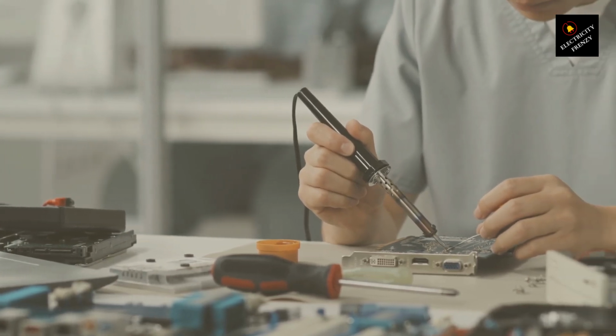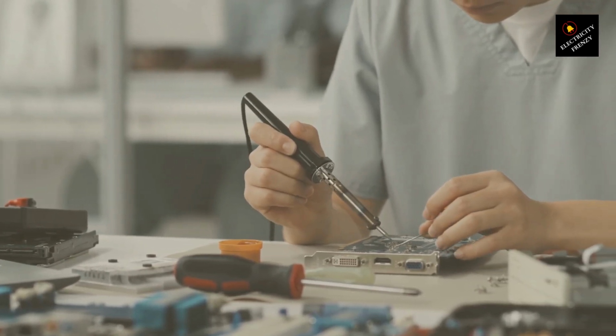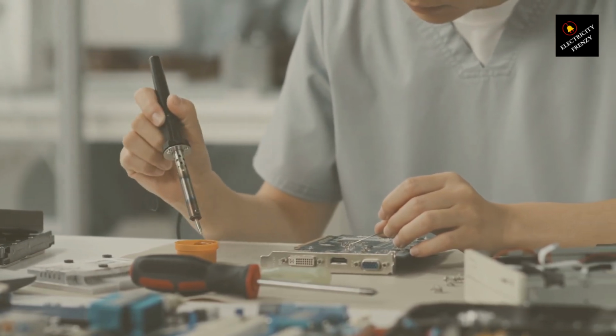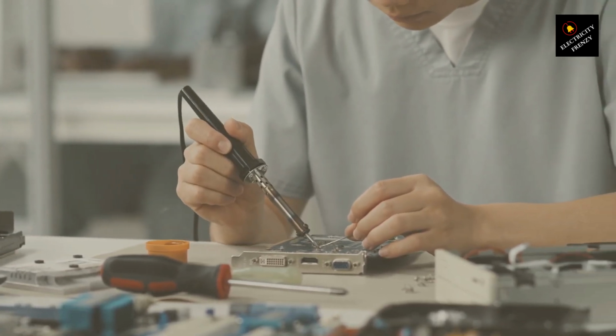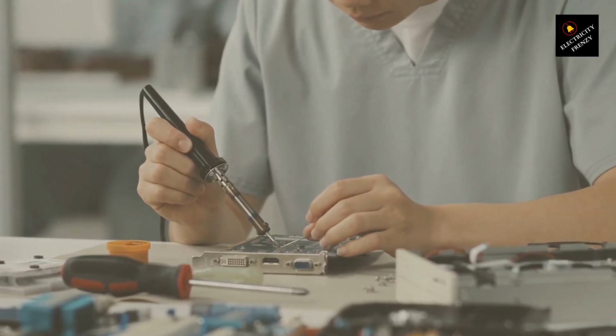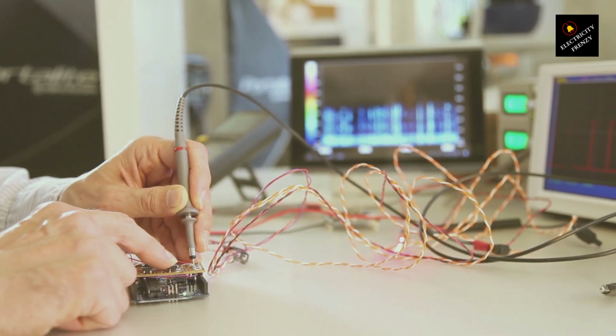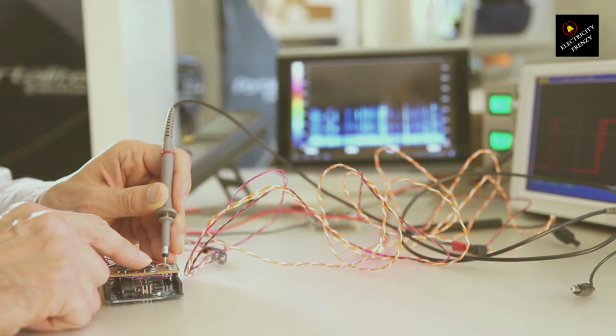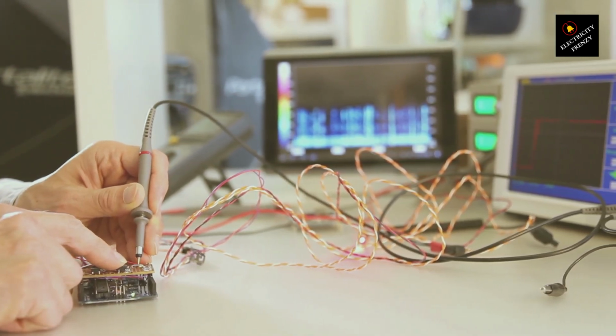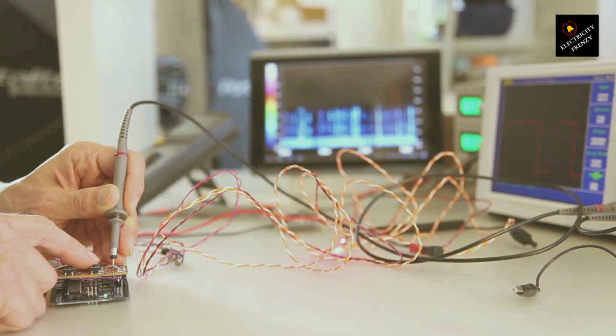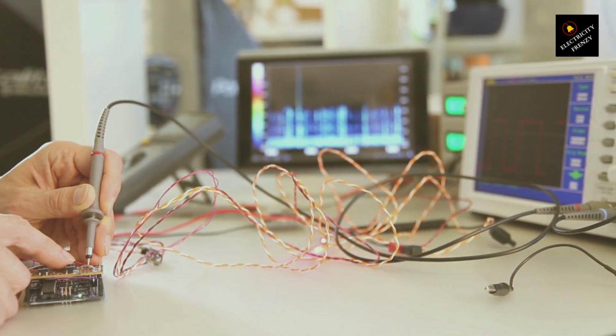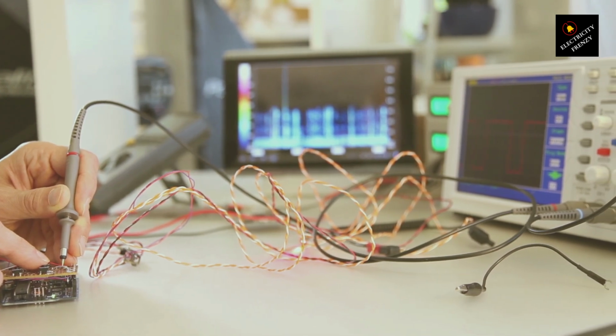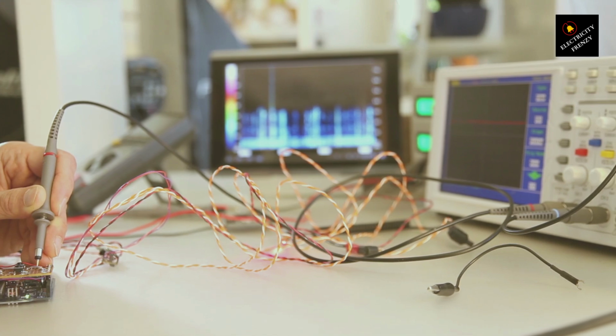It's all about the power rating, my friends. The power of the transformer must be higher than the power of the motor. Why? Well, if the motor demands more power than the transformer can handle, the transformer itself becomes the weakest link. It'll start to overheat as it struggles to keep up with the motor's thirst for energy. And just like the motor, if the transformer gets too hot, it's game over.